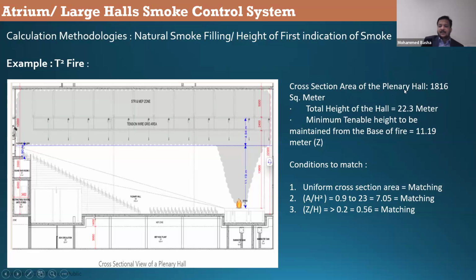The cross-section area of the plenary hall, the entire cross-section, is 1,816 square meter. I am not taking the volume, just the cross-section. Total height of the hall is 22.3 from the stage base to the top. Minimum tenable height to be maintained, I mentioned up to this point, which is 11.19 meter, which will not work because the smoke will come down very fast. But we are considering this level for the occupants.